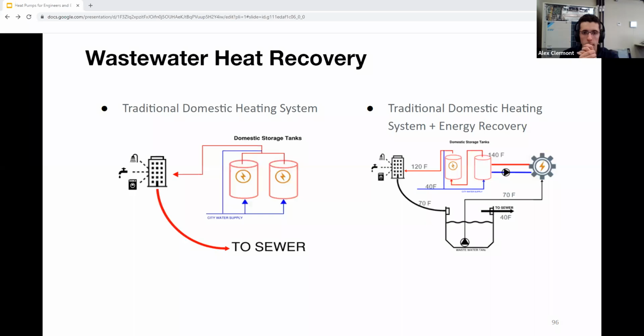Now, what we want to try to do is recover some of that heat before it goes into the sewer. The first step of this is to implement a wastewater storage tank to capture the water to recover heat from it. That water then gets pumped into a water-to-water heat pump, which we talked about in our intro to heat pump presentation. This machine transfers the heat from the wastewater to our domestic storage tank. With this wastewater recovery, we can hold some of the tanks at 140 degrees without using any additional heating source.